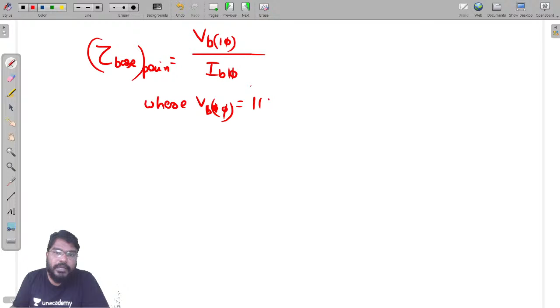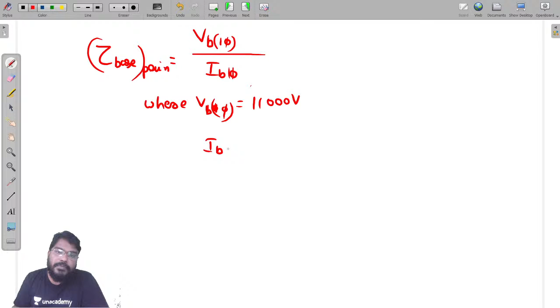So this value is equal to 11,000 volts. Now IB is equal to IB in single phase. For delta connection, it's IL by root 3. How do we get IL value? It's power S divided by root 3 times VL. So calculate this value: S divided by root 3 times VL.